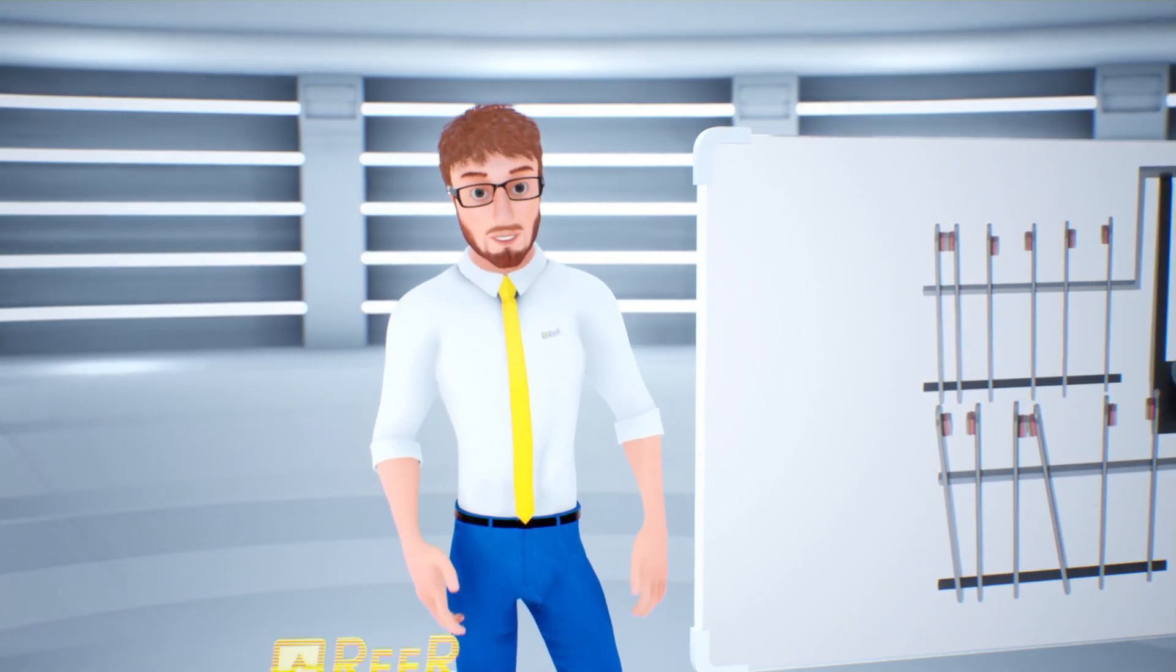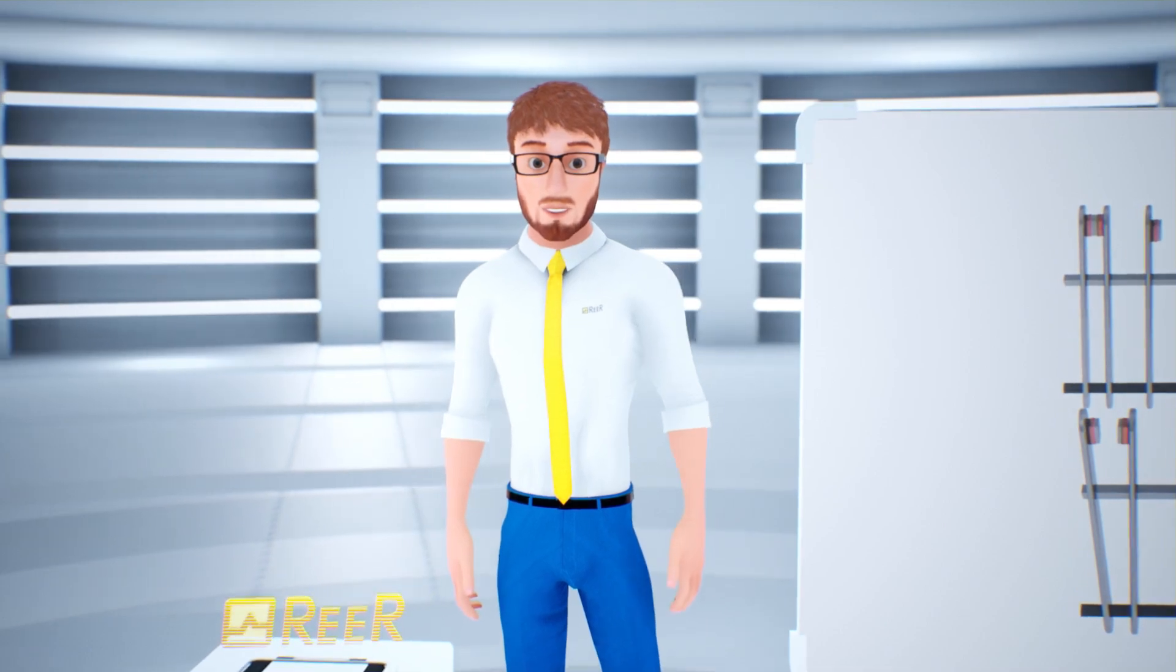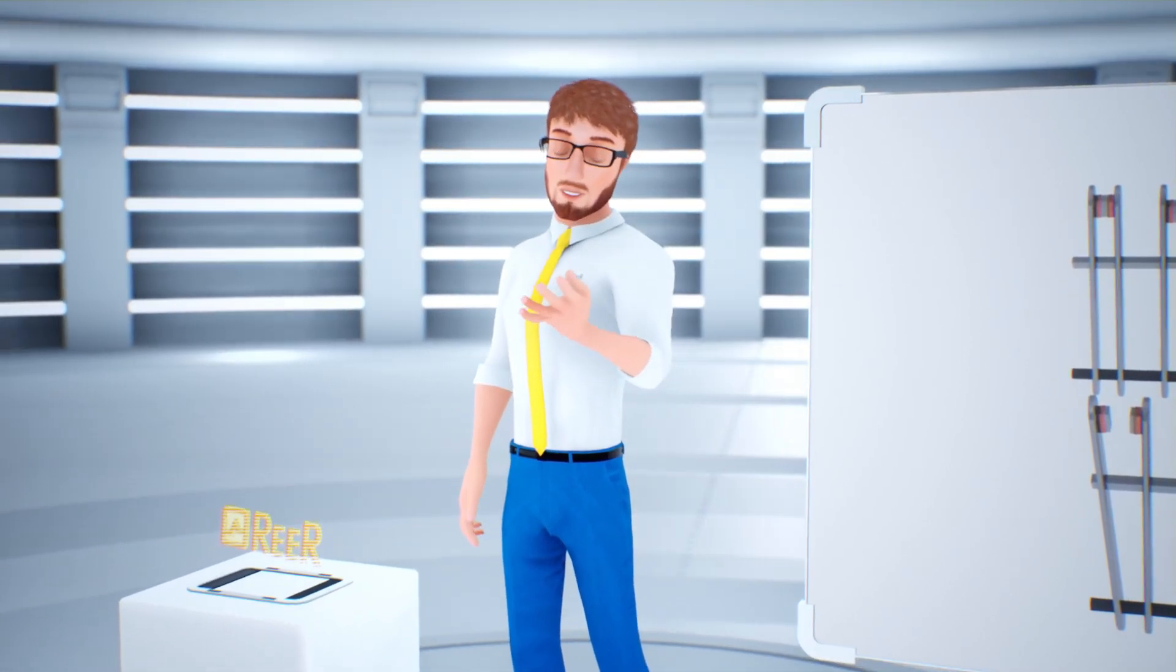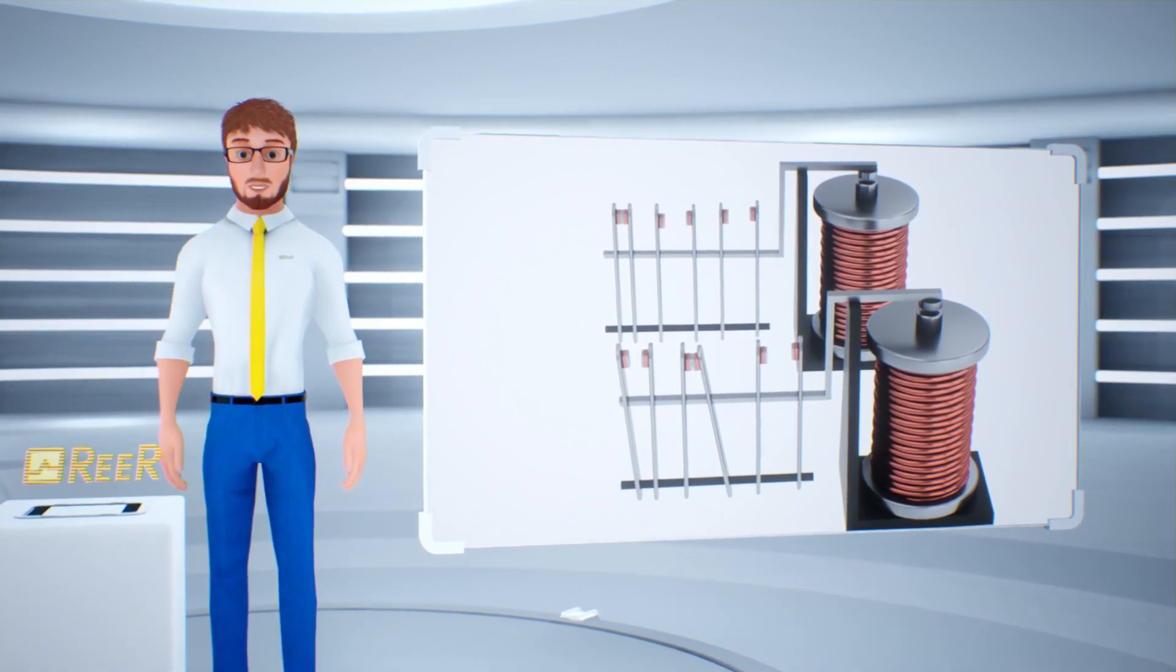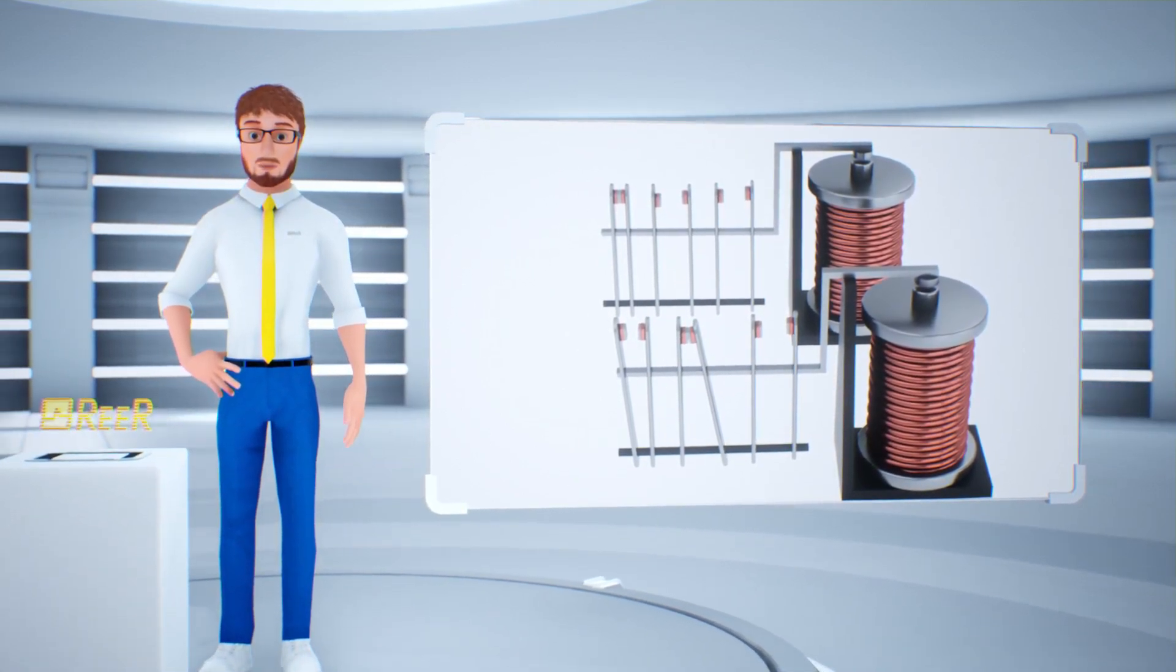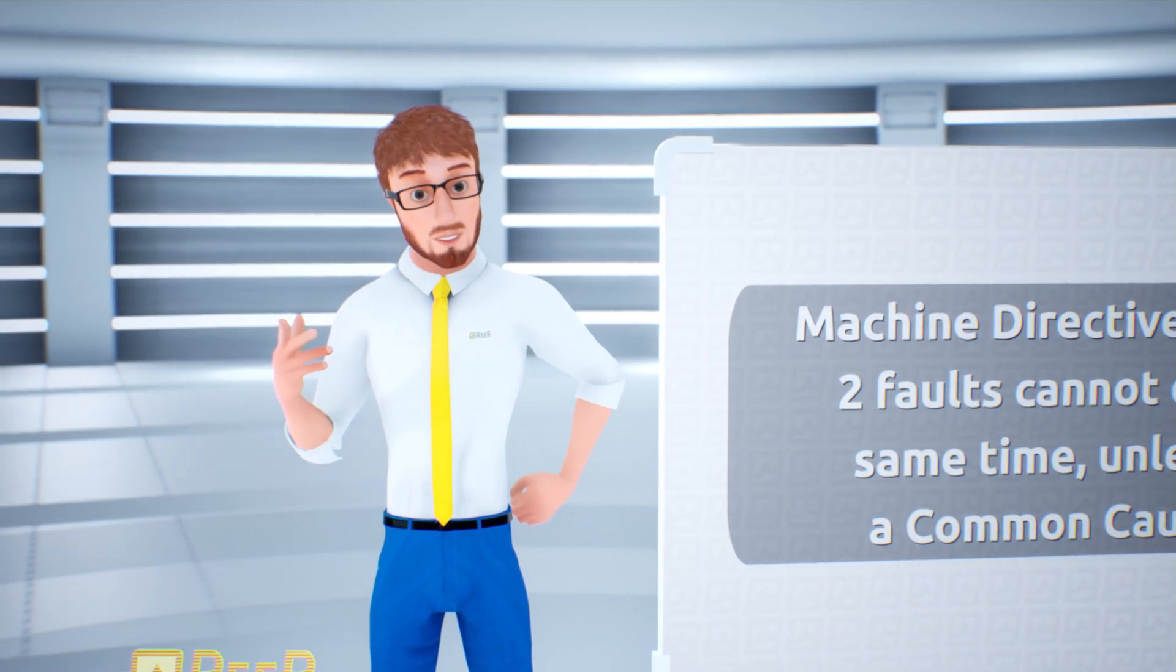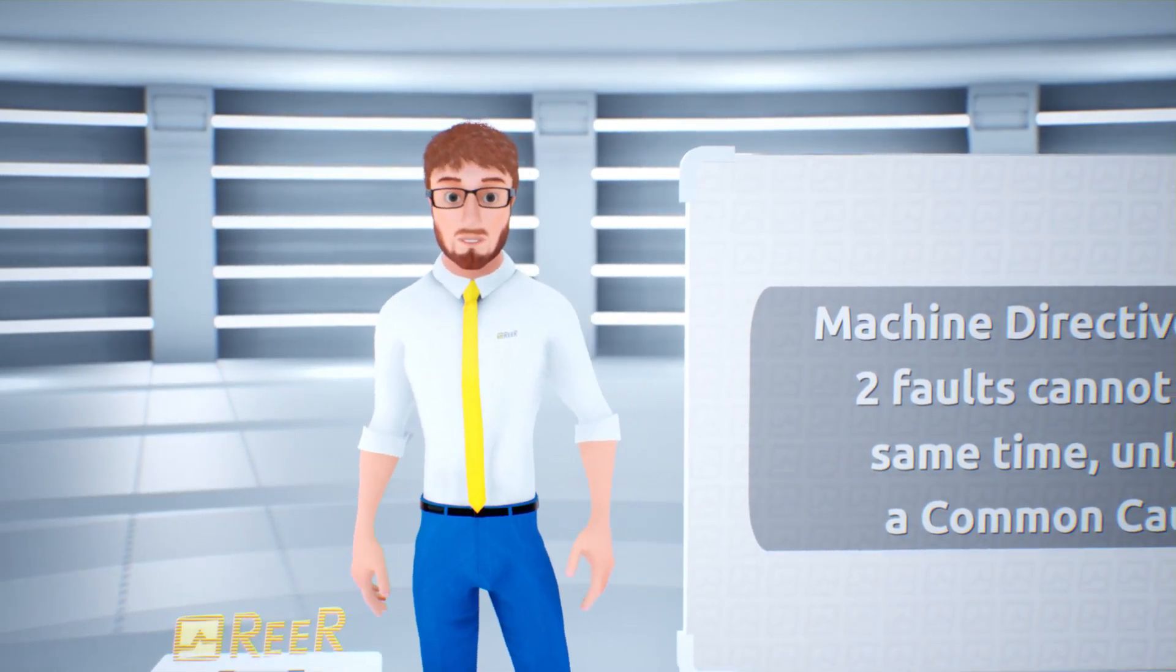The opening of the circuit is therefore guaranteed by the redundant relay, and the single failure on one of the safety relays does not compromise the overall safety of the machine. In fact, the machine directive defines that two faults cannot occur at the same time, unless there is a common cause of failure.